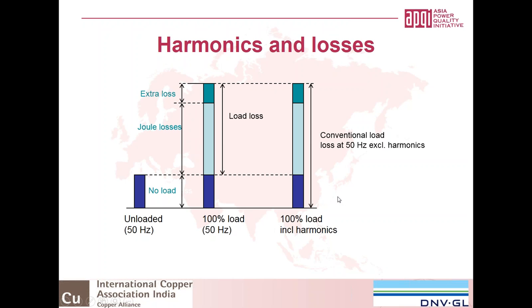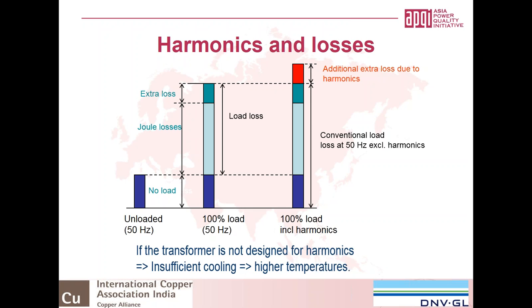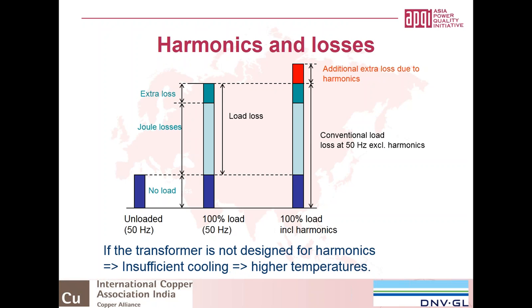for the transformer which is loaded with harmonics, except we will also get some additional losses due to the harmonics, some extra losses. And if you counted on the total losses being on this line together with the 100% load, and you didn't mention that the transformer will be used in an extra harmonic environment, the transformer will get that red area as additional losses. But the cooling isn't made for that. So it will mean that you get a higher temperature as mentioned before, and probably in case you're running this transformer for a long time, you might really have some failures within the transformer.